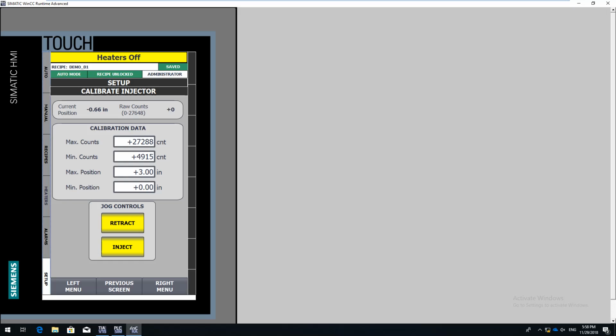Ideally, though, when you're adjusting your linear pot, you want to make sure that you are not in any form of dead zone for the linear pot. Even though you are still able to travel up and down on that linear pot, you do want to watch your raw counts. You do not want to be anything near the 27,648. In this case, I'm a few hundred counts below that, but I do want to be able to see that as I'm moving the injector up and down, I am seeing my counts adjust. If the counts are not updating anymore, you're into the limit of the linear pot, and thus you might actually have a dead zone and not actually be able to see anything accurately.